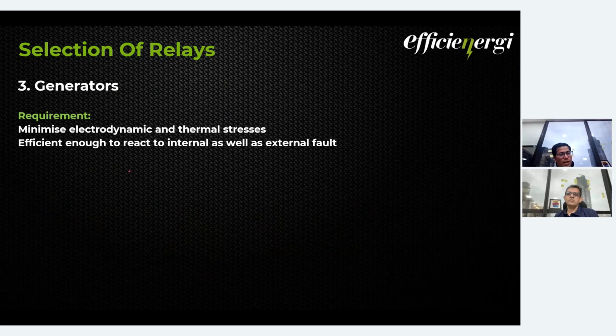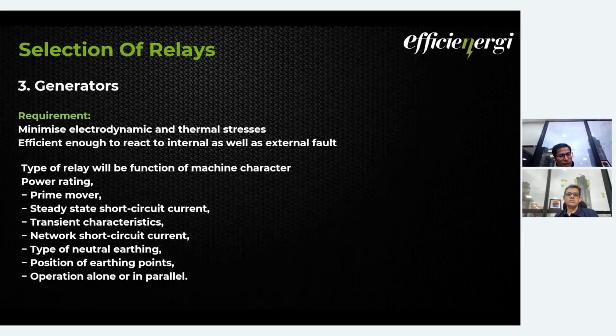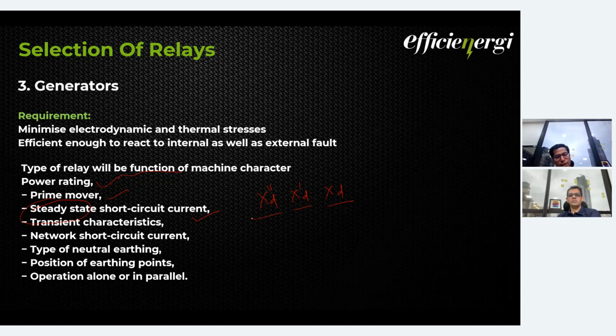For generators, there is a long list, because the relay function is based on power rating, prime mover, and steady state short circuit current, if you know the decrement curve or the reactance that comes across at different times. These three reactances come across at different times when there is a fault. Initially it is a subtransient, then a transient reactance, and then a steady state reactance. This is very high, maybe 25% to 30%. This is at a lower level of 10%. When the fault occurs, these two diminish in maybe 5 or 10 cycles, and after that this comes into the picture, which is very high.